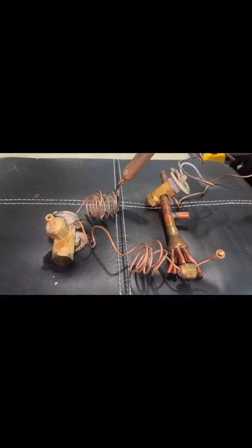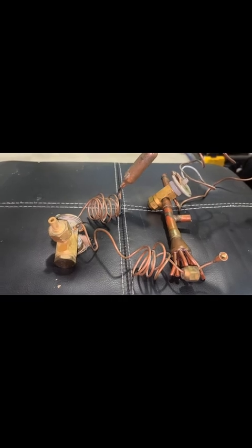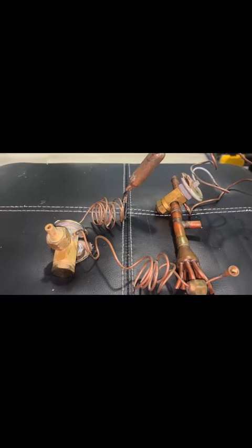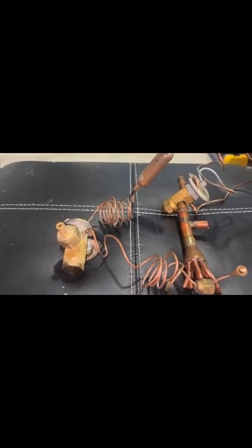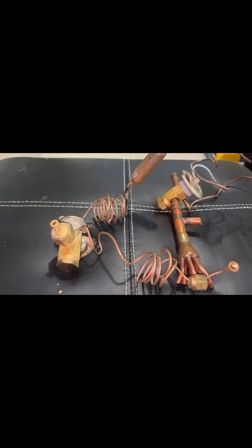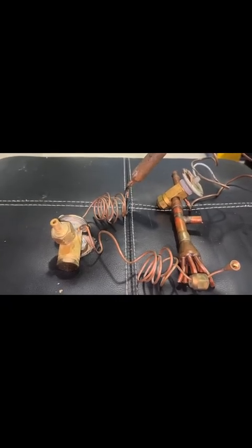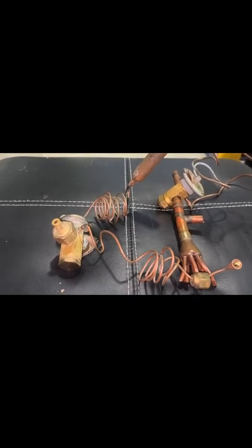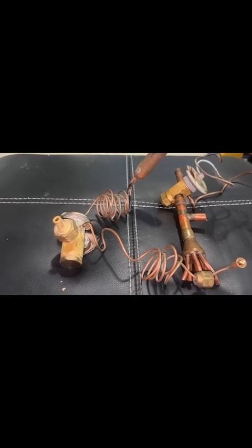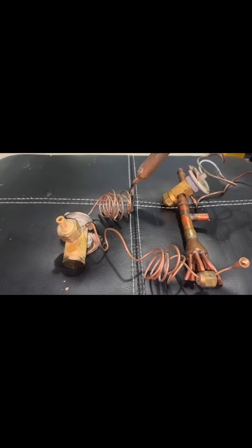The key difference is control. Okay, the pistons offer a fixed flow, while your TXVs dynamically adjust refrigerant to match the cooling load, preventing liquid flow back and improving performance. Now, for your system charging methods, the primary method of charging a system changes based on the type of metering device you are dealing with. A piston system uses the superheat method of charging, and a TXV uses the subcooling method of charging.